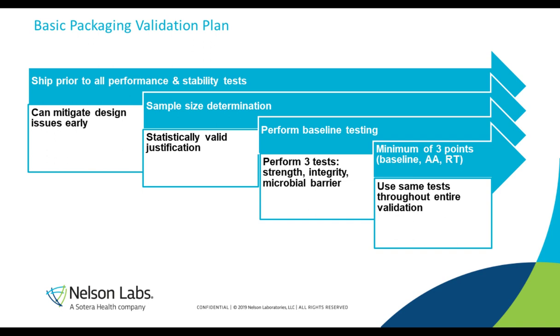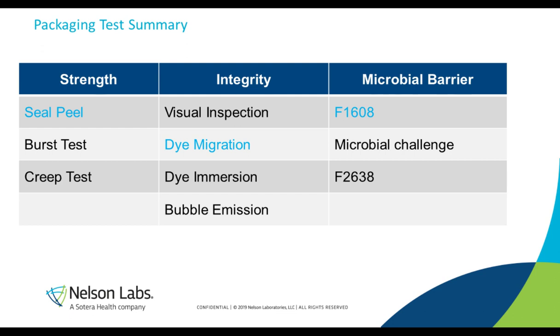Then we're going to look at an accelerated aging time point. This is the optional aspect of establishing your shelf life. And then finally, real-time aging, which is the requirement. It is important that all 3 of these aspects start at exactly the same time. There were some situations where clients were just doing their accelerated aging and not doing real-time aging, but that is not acceptable. Real-time aging is the requirement, just to reiterate.